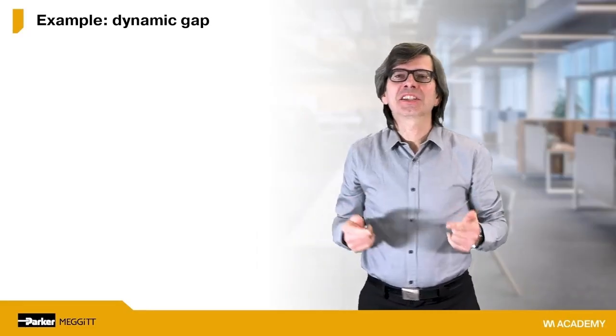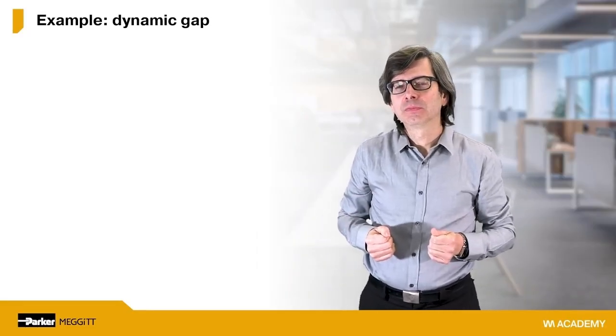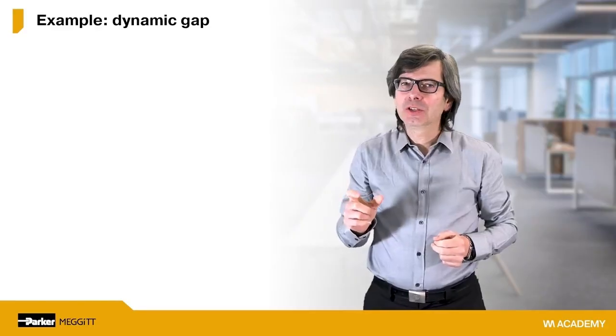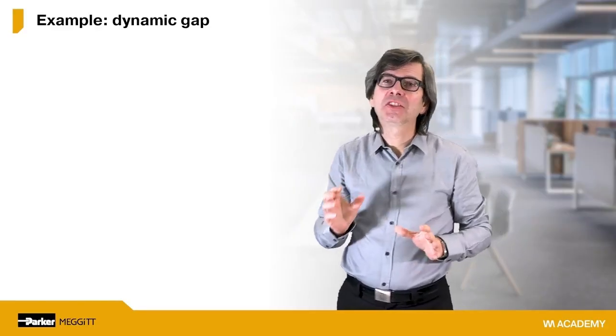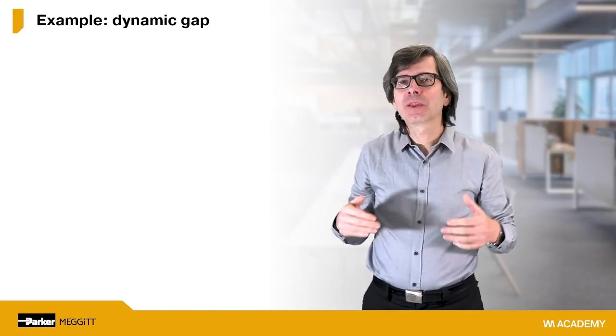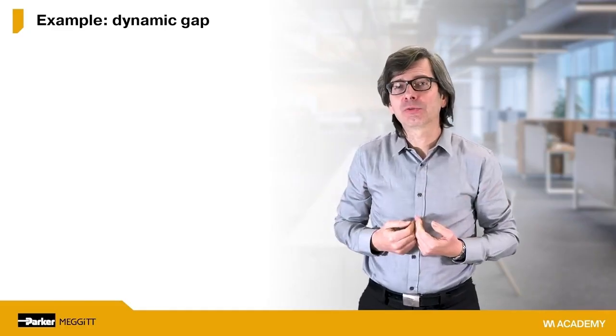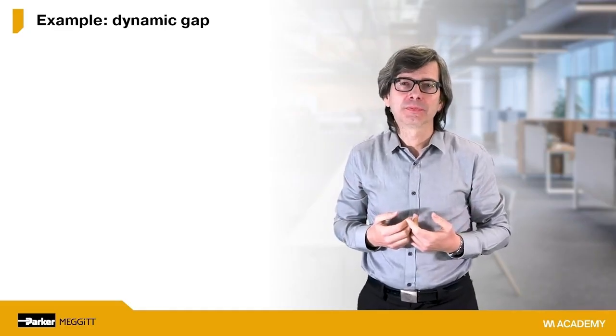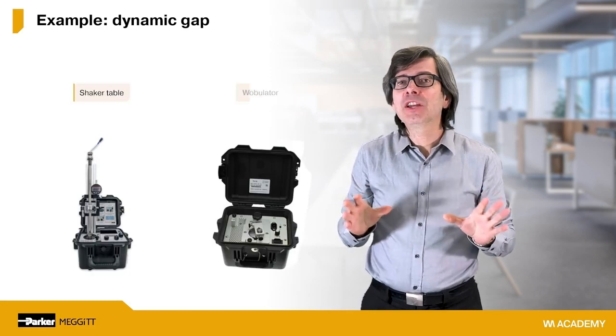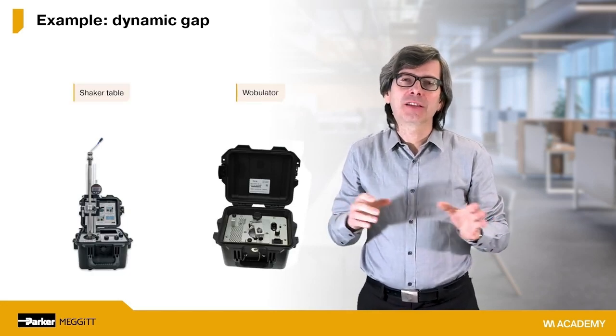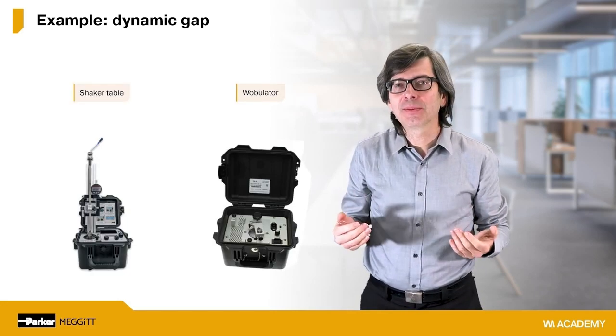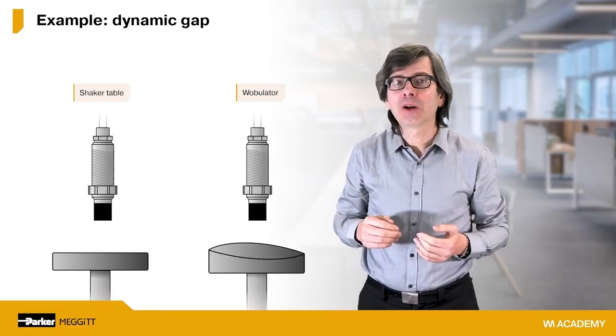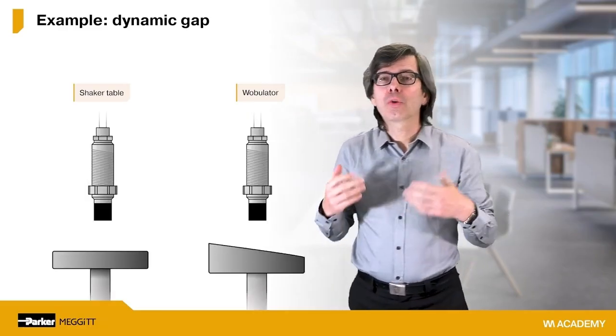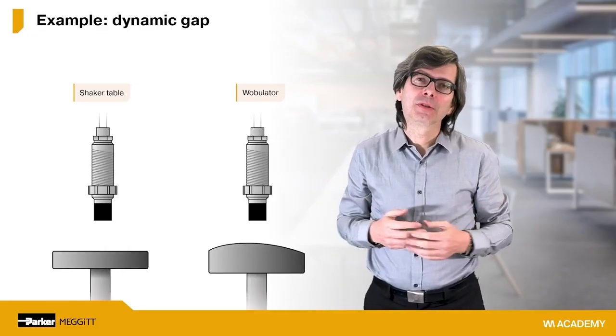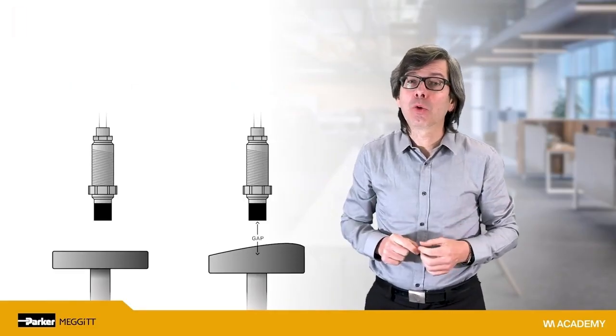Now let's discuss another type of changing gap. This type of gap change is not static. Instead, it's dynamic and it's caused by the vibration of the target, which is usually a shaft. We can simulate vibration by either attaching a target to a shaker table and then affixing a probe above the target, or by using a wedge-shaped rotating plate known as a wobulator.